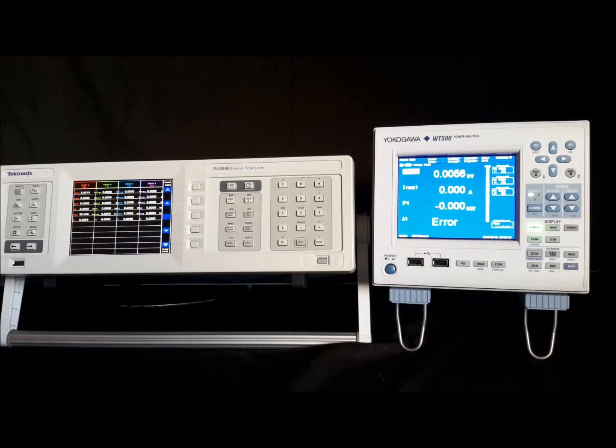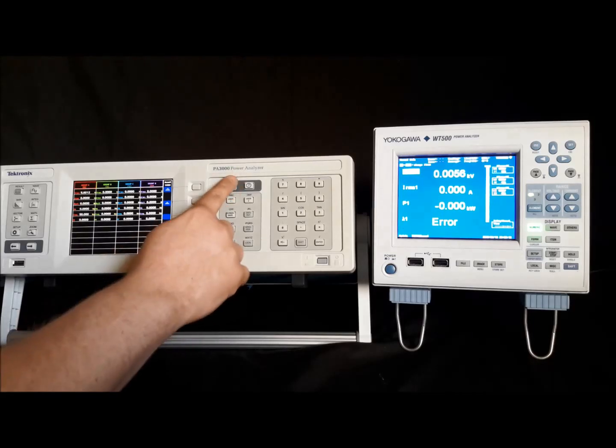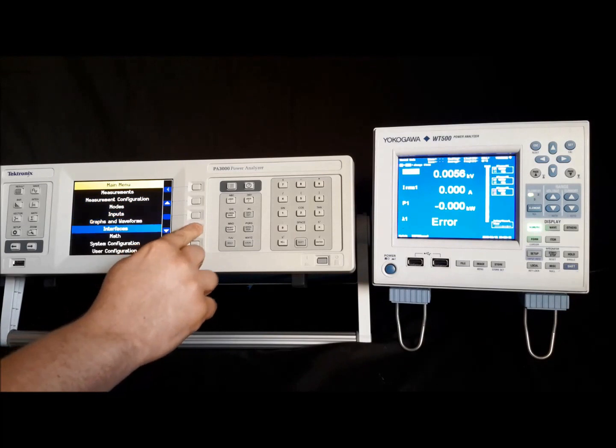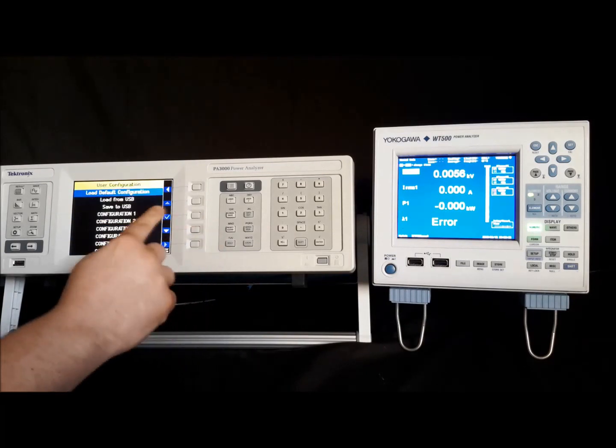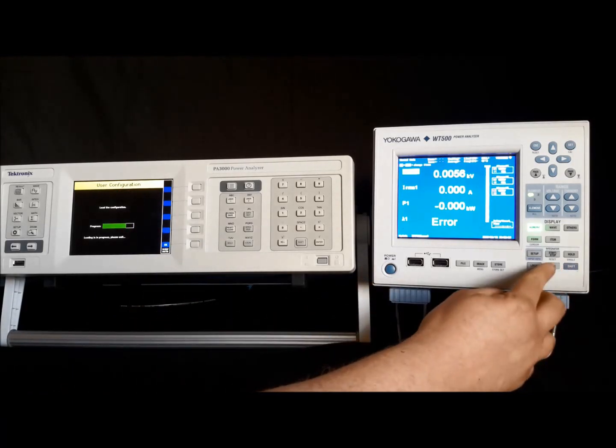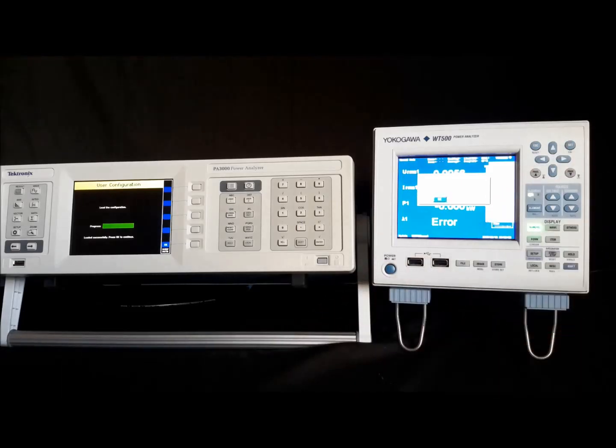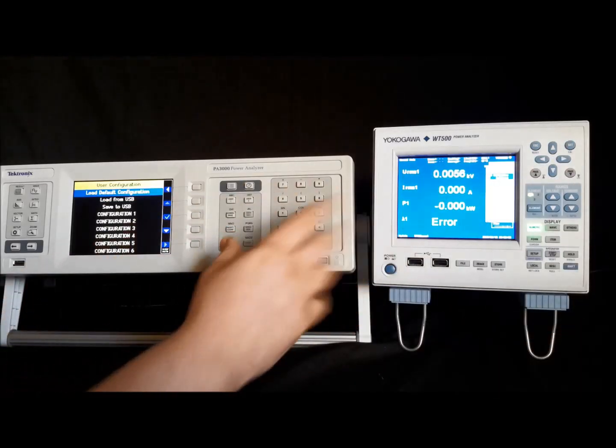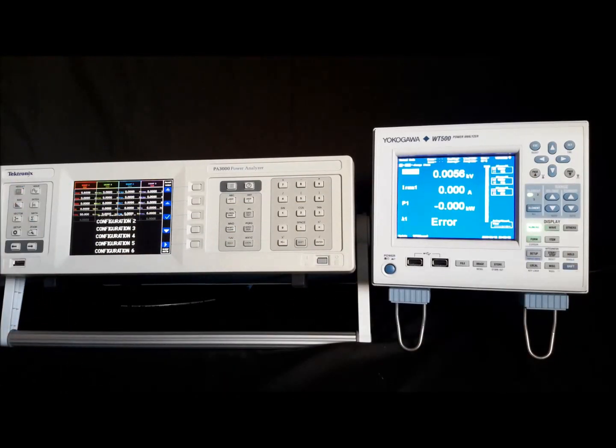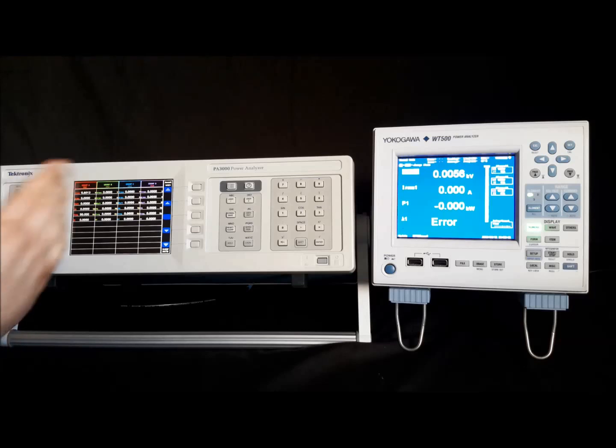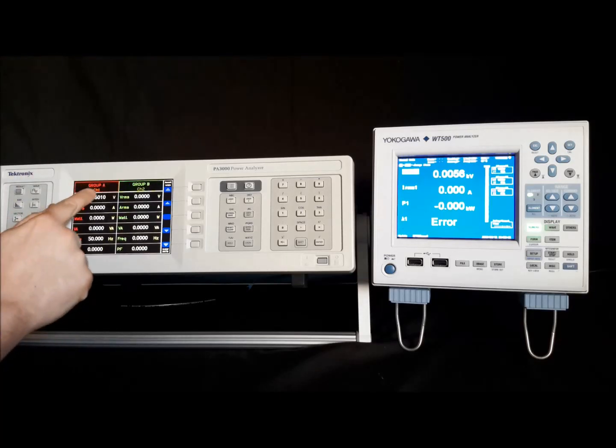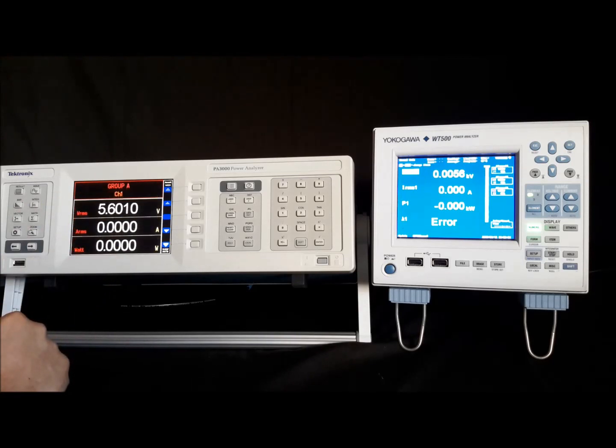So first things first, I'm going to default both units to show there's no magical setup. Let that load. Okay, so both units have been set to their default settings. Now, the display on the Tektronix shows each of the 4 input elements. Because I'm just looking at the one, I'm just going to focus on Group A, which will be channel 1, as you'll see across the top. Next thing to do is to set up the auto ranging, which I'll be using on this test or comparison. I'll also set up the external shunts as well.